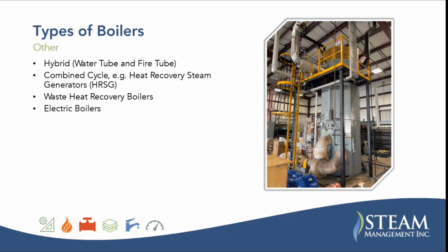And then we have electric boilers, which are coming up more and more. I've evaluated these for a few clients. So far, the operating cost and the initial install cost outweigh the benefit, but I'm predicting they're going to start having a bigger place in the world as we move towards decarbonization.